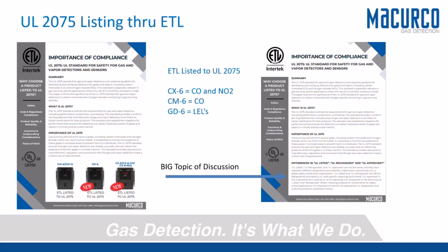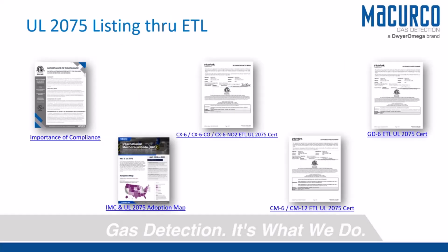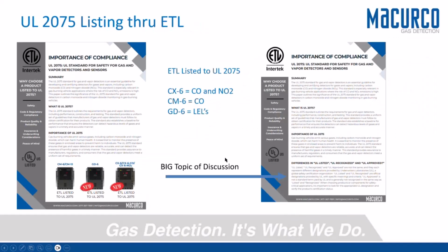If you look at the right side and follow that arrow, let's start backwards. The biggest understanding is to make sure you know the difference between a UL listed, a UL recognized, and a UL approved product. If you cannot find a cert with the part number of the product you're looking at with UL certs on it, it's not UL certified. So if we go back one slide and you don't have an actual document with the parts and nomenclature, it's not fully listed to that part or that header for UL.